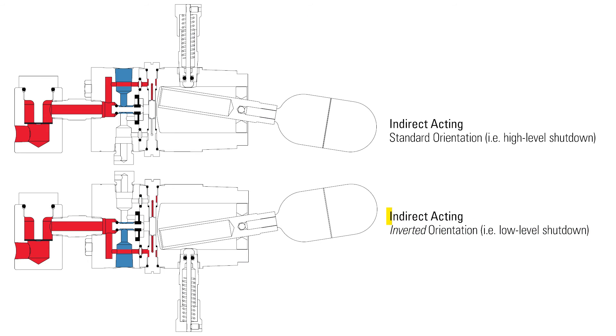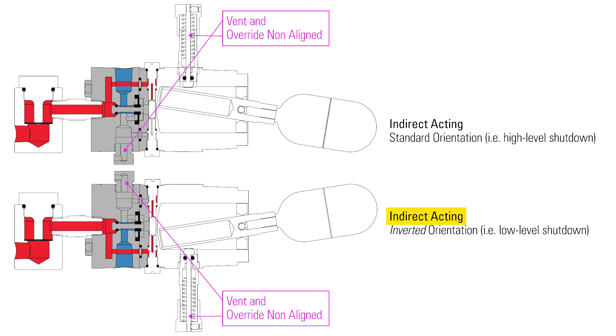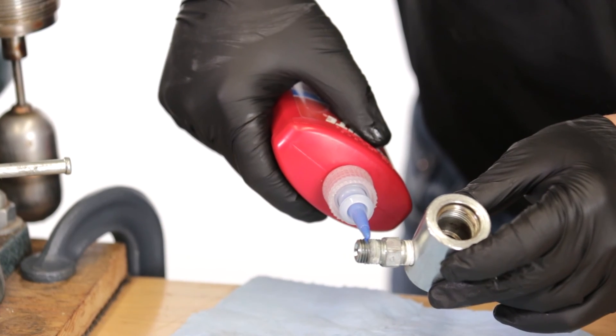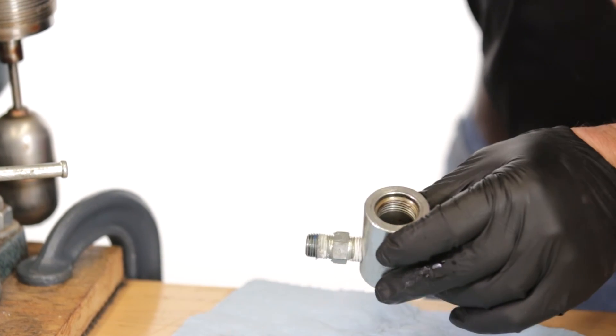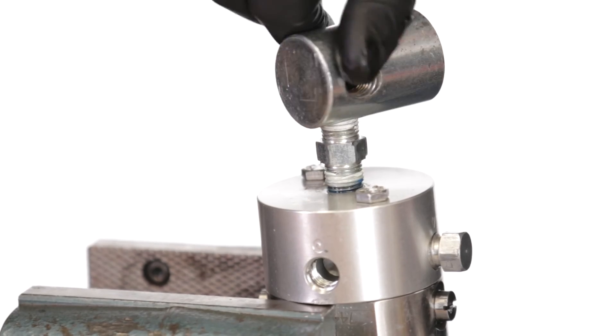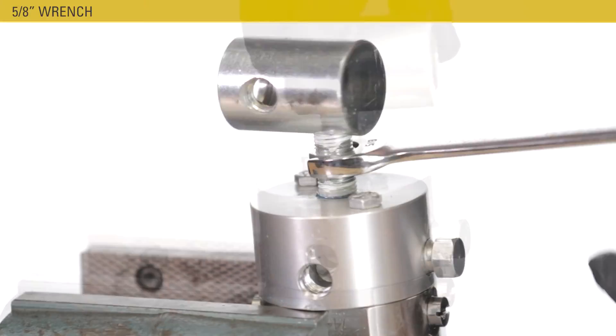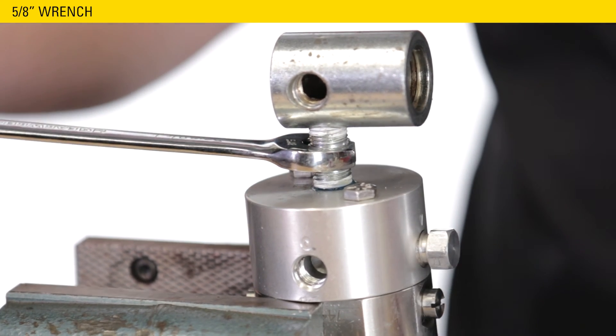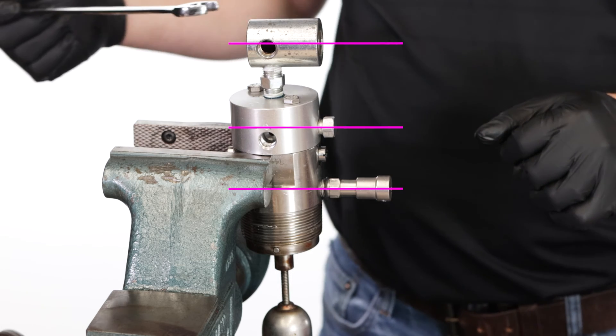For indirect acting, turn the pilot body so the vent plug is 180 degrees from the override. Apply primer and Loctite to the end of the nipple. Both ends if you fully remove the nipple from the filter body. Install the filter and nipple onto the pilot body using a 5-8ths wrench. Orient the filter body in line with the other features on the housing.